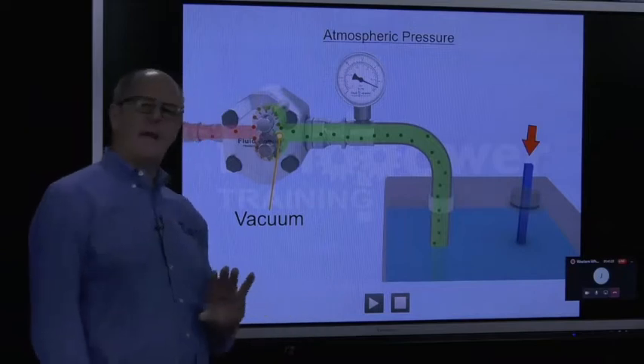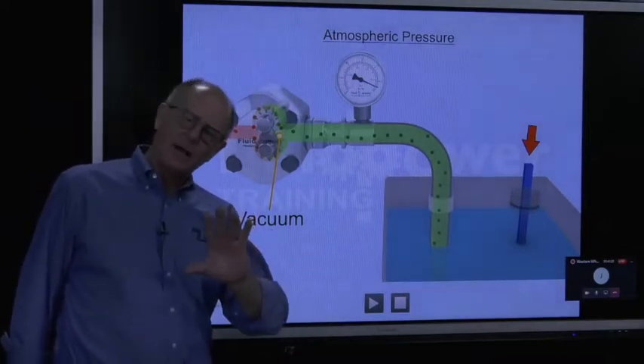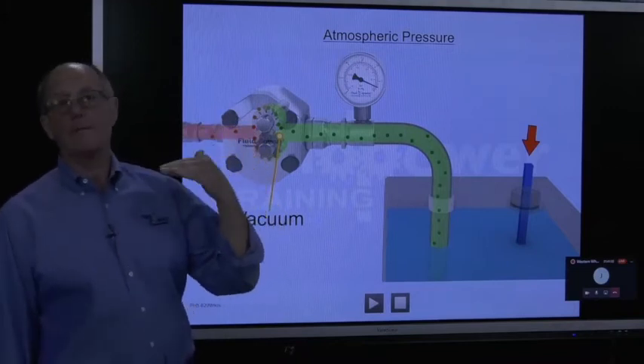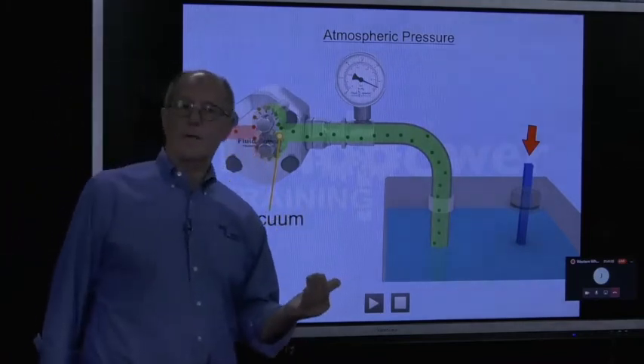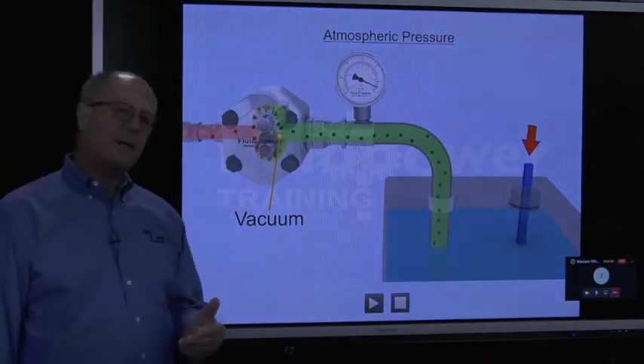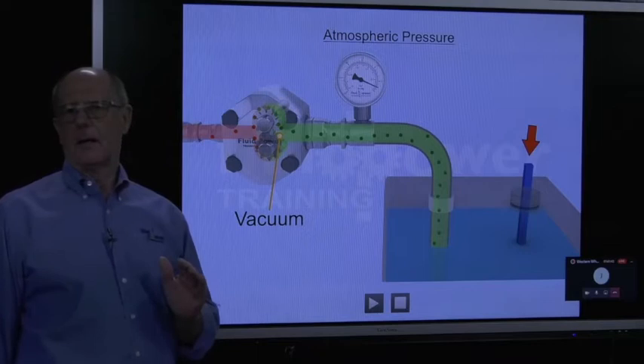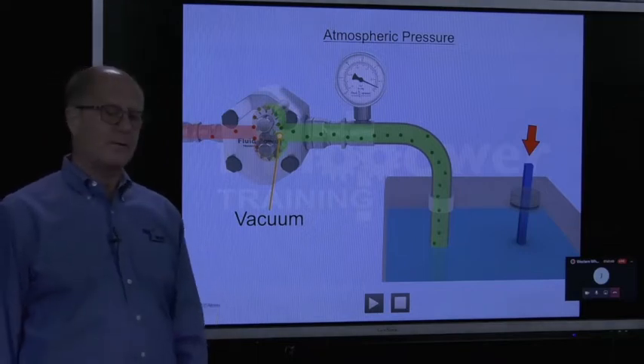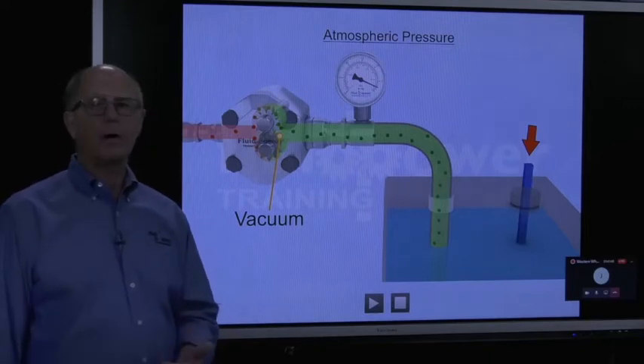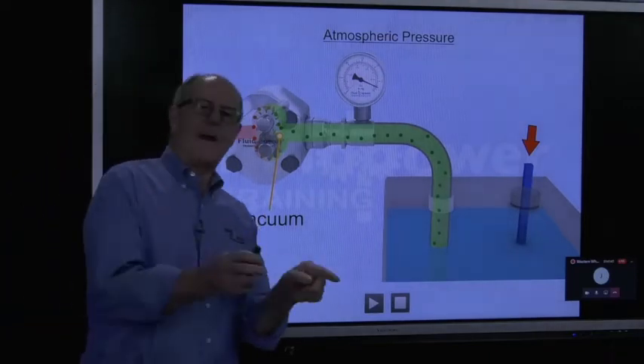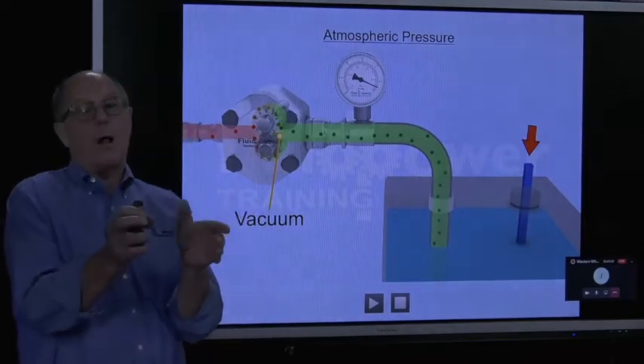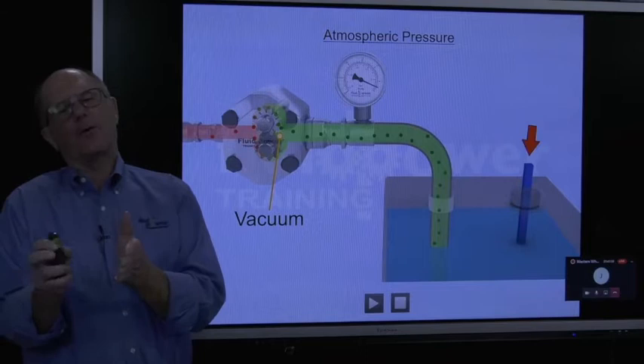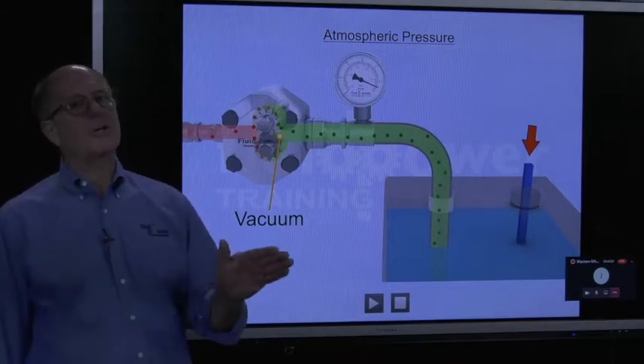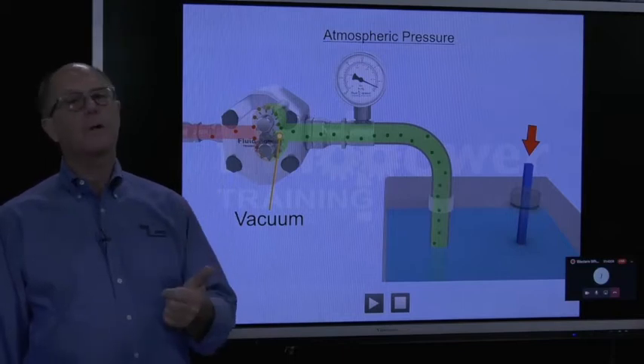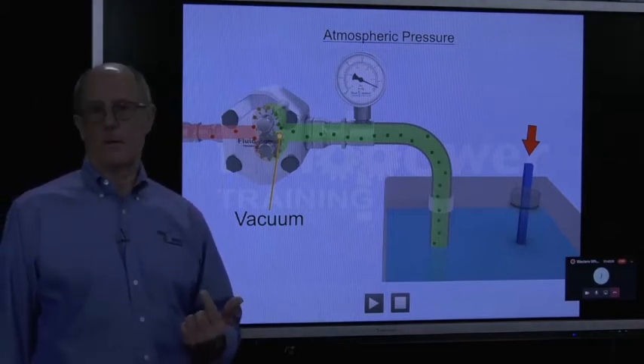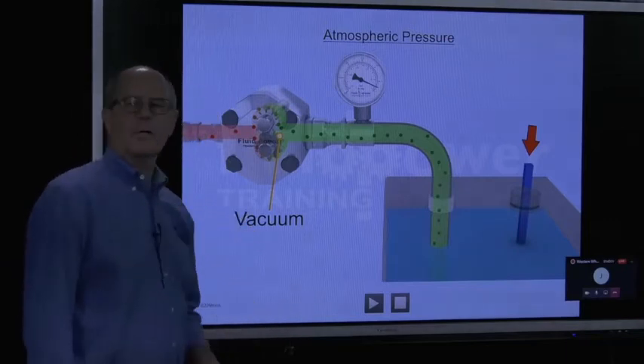So you can see this is a very, very delicate part of your hydraulic system, because in reality, relative to your elevation, at sea level atmospheric pressure is 14.7 psi, but in Denver, Colorado, where you're 6,000 feet above sea level, you're at 12.1 psi. So keep going up and the pump won't work anymore. And that's one of the reasons why we say the manufacturer's job is to make sure that the inlet restriction is well within the specification set forth by the respective pump manufacturer. Because if you're marginal, you're in trouble if you get into cold temperature, number 1, and if you go into a higher elevation, number 2. So that's how it works.